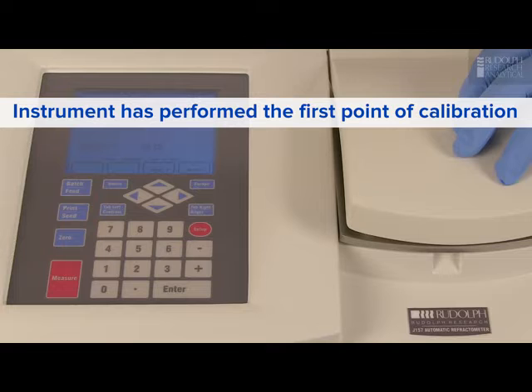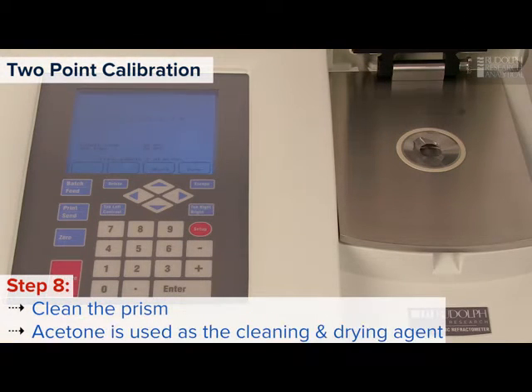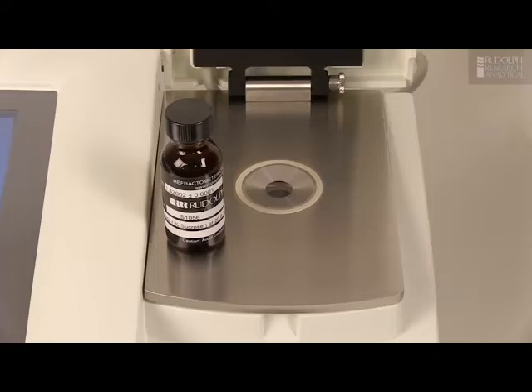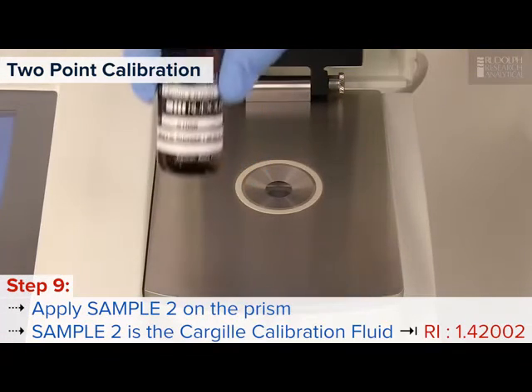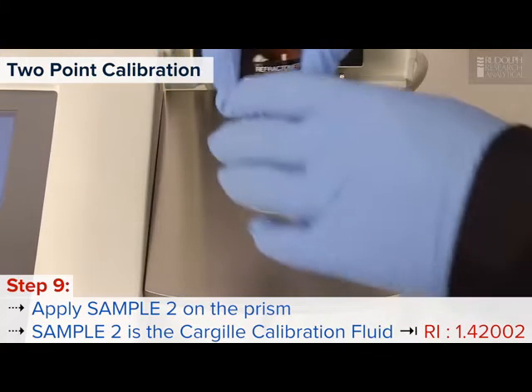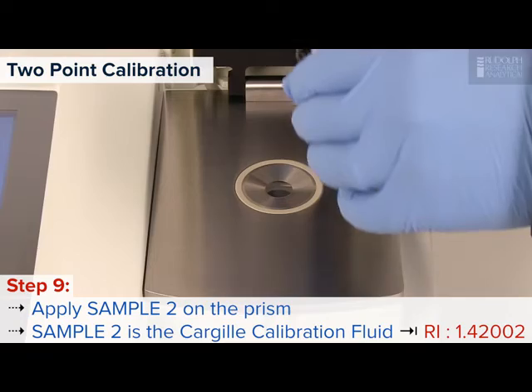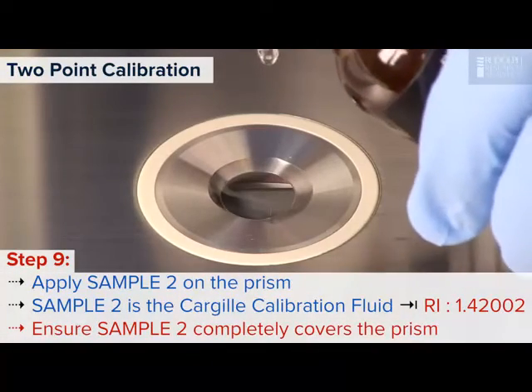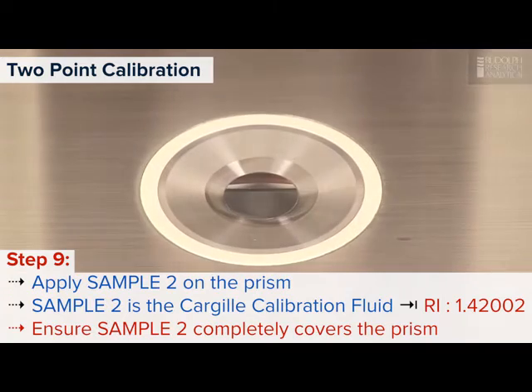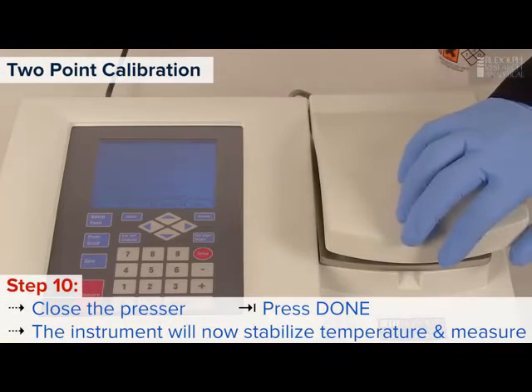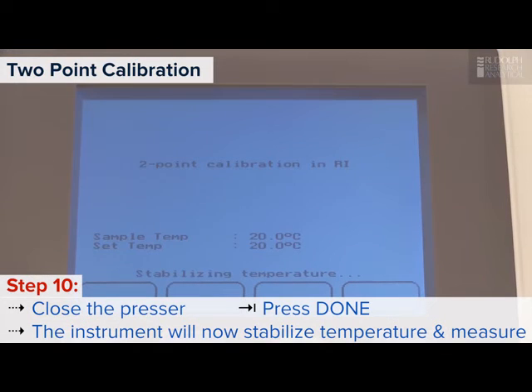and press enter. Now that the system has performed the first measurement of the 2-point calibration, we're going to clean the water off the prism. We're going to use acetone as a cleaner and dryer agent. And we're going to apply the second standard onto the refractometer prism, ensuring that the refractometer prism is completely covered by the sample. Now we're going to close the presser lid and press Done. The instrument again is going to stabilize temperature. It's going to measure the sample, and at the end it's going to ask you to input the value.